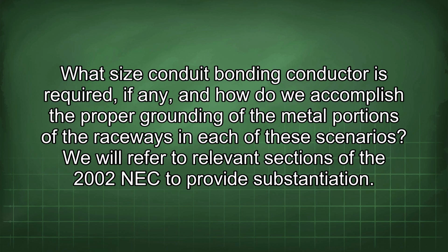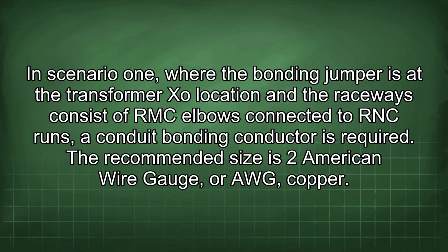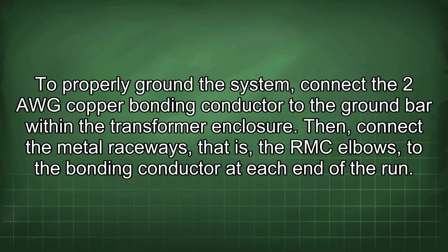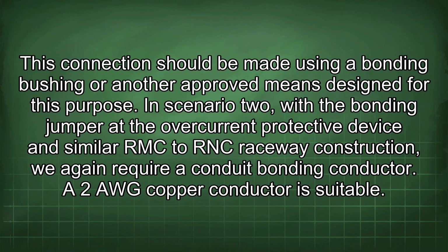We will refer to relevant sections of the 2002 NEC to provide substantiation. In Scenario 1, where the bonding jumper is at the transformer XO location and the raceways consist of RMC elbows connected to RNC runs, a conduit bonding conductor is required. The recommended size is 2 American wire gauge, or AWG, copper. To properly ground the system, connect the 2 AWG copper bonding conductor to the ground bar within the transformer enclosure. Then connect the metal raceways, that is, the RMC elbows, to the bonding conductor at each end of the run. This connection should be made using a bonding bushing or another approved means designed for this purpose.